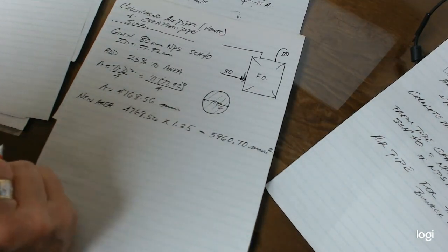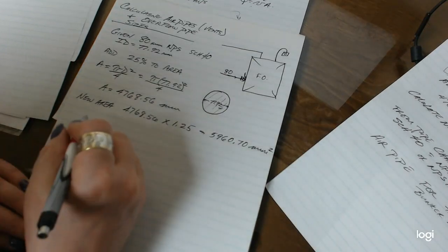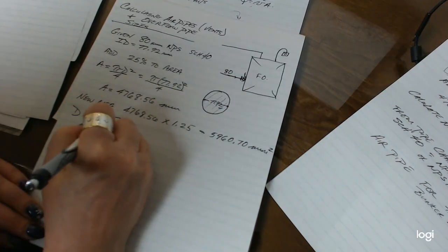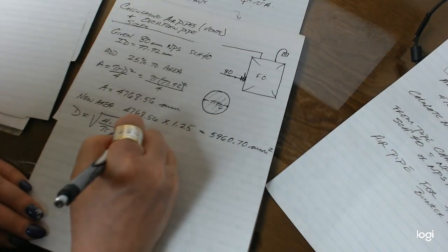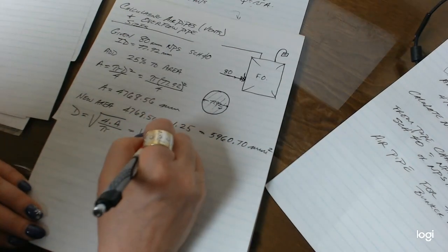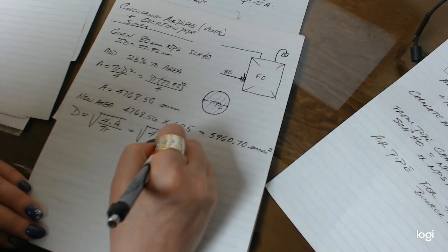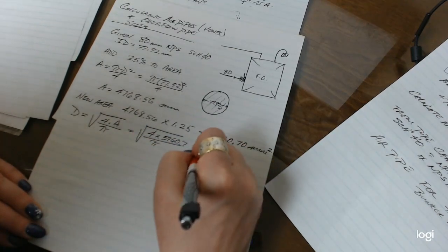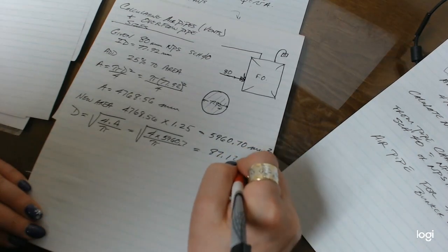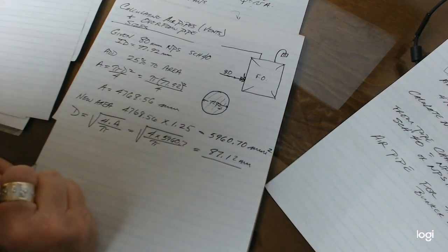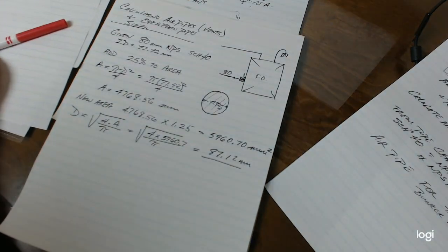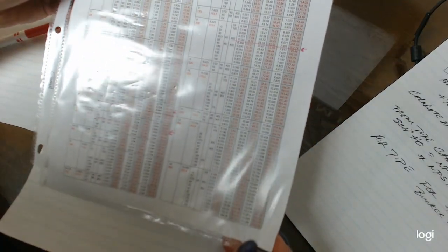Now what I want to do is go back and calculate my new ID for my larger pipe. So in doing so, I go D is equal to the square root of 4 times A divided by pi. And in this case, I'm looking at the square root of 4 times 5,960.7 over pi. And my new ID is going to be 87.12 millimeters. So now I go back to my pipe chart that I've shown you guys before. And once again, this is online because it's very small.